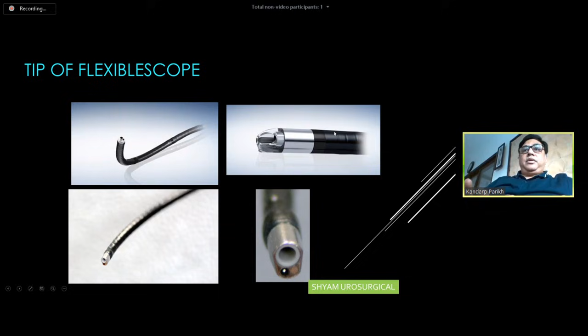Now, if you again have a closer look at the tip of the scope, here there is a blue color marking. This defines a bending section. This is from where the bending happens, and there is a 270-degree deflection achieved on either side. So this part by default has to be above the tip of the ureteral access sheath, and that is the reason we put the ureteral access sheath below the UPJ or in the upper ureter, so that this blue part remains outside, so it gives you a maximum deflection. Otherwise, it will not. If you want to go into the lower calyx, and if this part is in the ureteral access sheath, then you will not be able to produce a proper deflection, and you may damage your scope also.